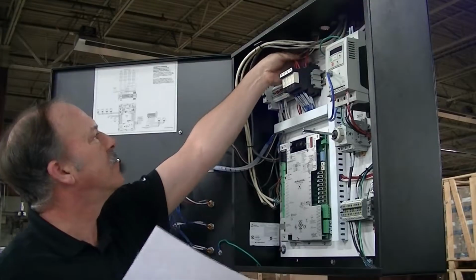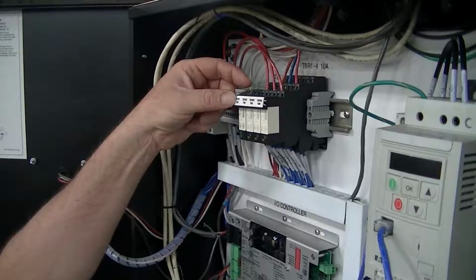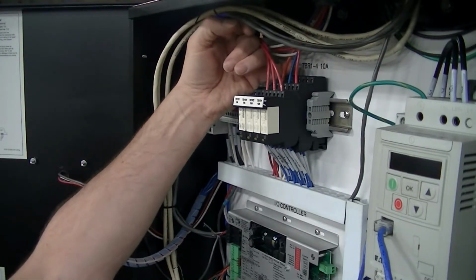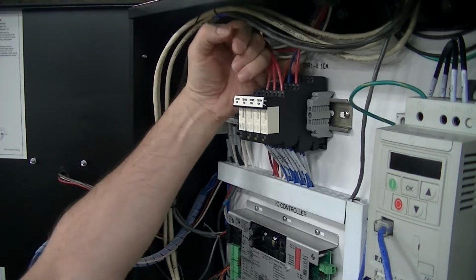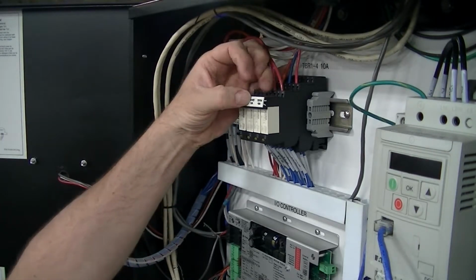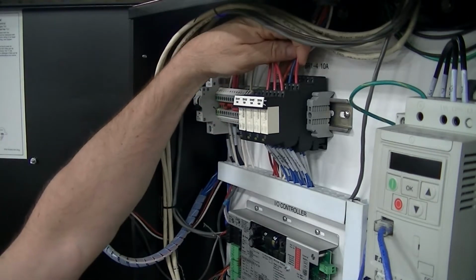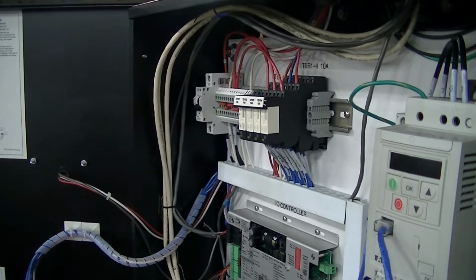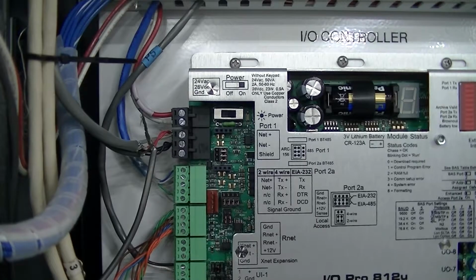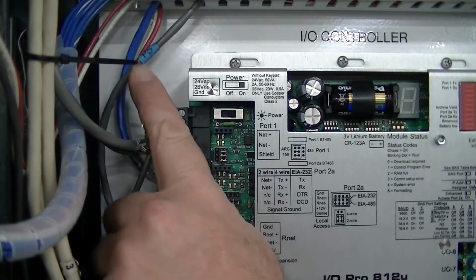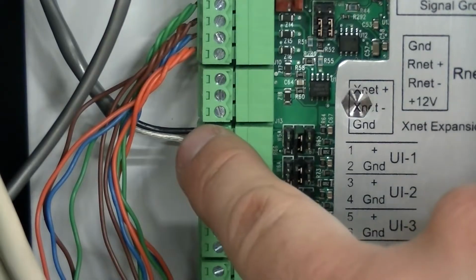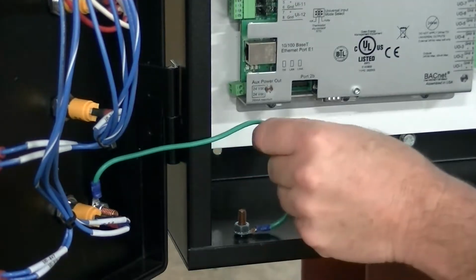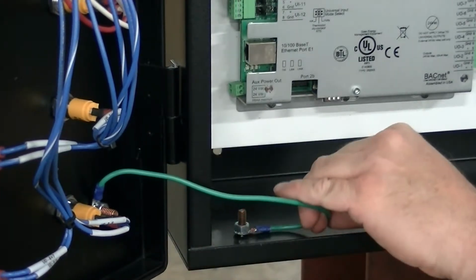Make sure the installing contractor has zoned the burners based on the drawing. Up to 4 zones can be used on each control panel. Check to make sure the wire connections to the zone relays, burners, and 1 thermostat for each zone is correct. Ensure the wiring for the pressure switch at the vacuum pump is connected to the correct terminals. Make sure all grounds are connected and secure in the control panel.